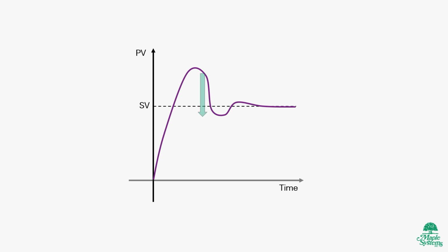So there's something called residual deviation. This is the difference between the target value or set value and the controlled variable or process variable. To overcome this deviation, integral is used. So when you use proportional and integral together, the target value or set value is easier to reach.